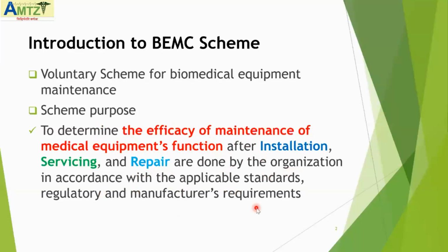And let's see how this purpose can be achieved. We have put some criteria to make sure that the equipment is maintained in the right manner, as well as to take care of the safety aspects of the patient, because if the equipment is not properly maintained, two things can happen. First is downtime, where the equipment is not working, and also it can put a hazard to the patient when such equipment is connected to the patient. It may give incorrect values also.